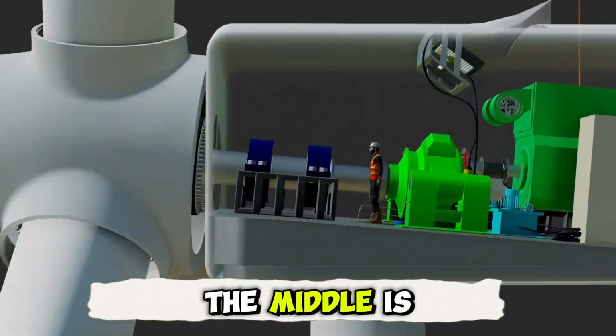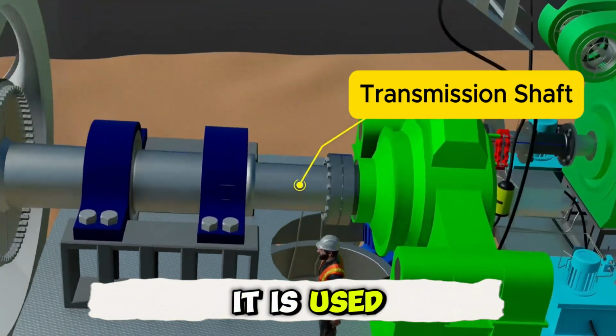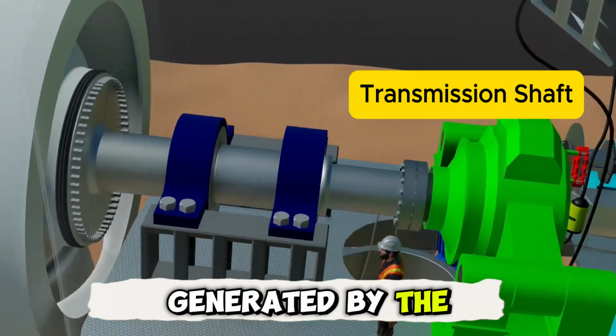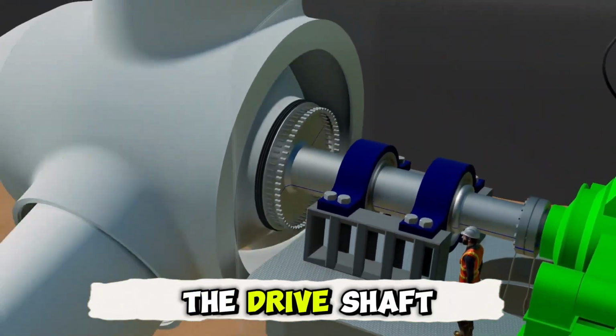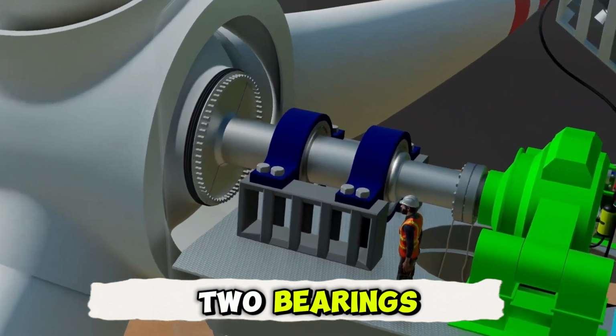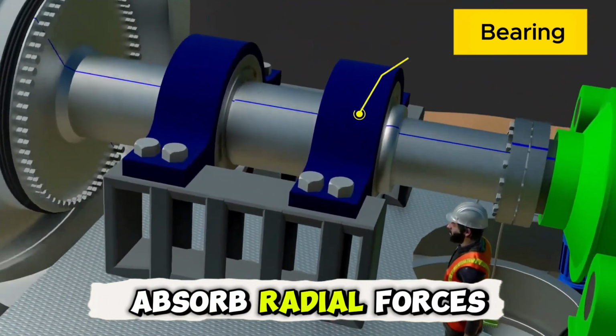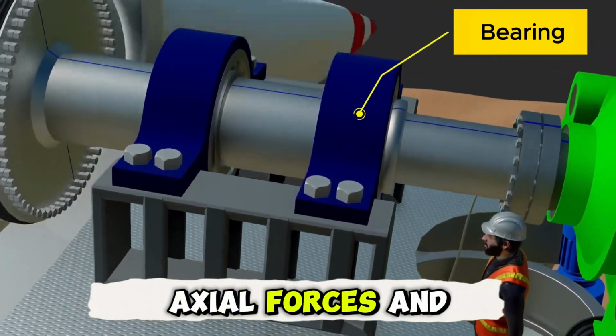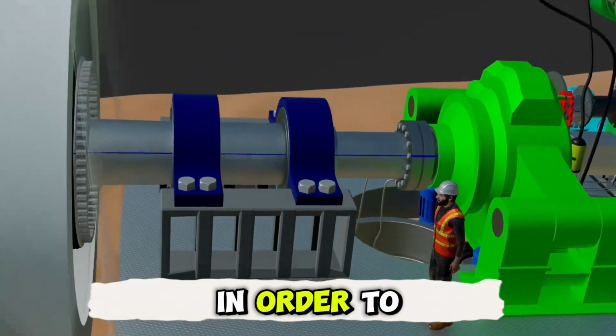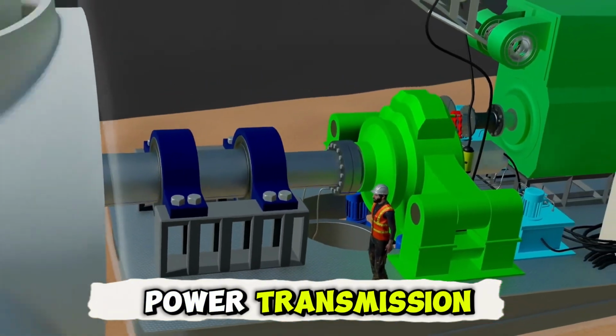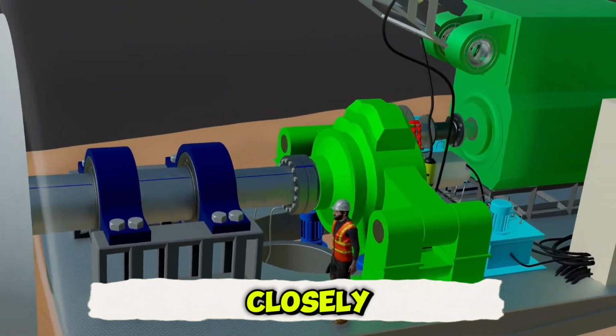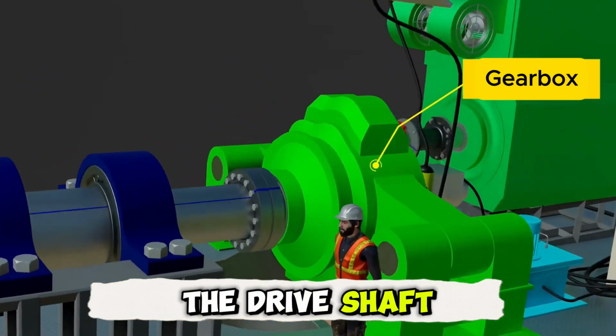This shaft in the middle is the drive shaft. It is used to transfer the torque generated by the blades towards the back. The drive shaft is supported by 2 bearings. The bearings can absorb radial forces, axial forces, and other mechanical loads in order to maintain the stability of power transmission. If you look closely, you can see the inside of the drive shaft is hollow.